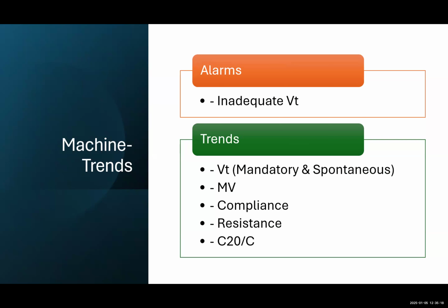Trend means I might come in the morning at 8 o'clock or 9 o'clock for my rounds, but how was the baby from the night, 12 o'clock to 8 o'clock? The machine gives me a record. In this, the alarms are very important. If the machine is alarming for inadequate tidal volume, that means either the lung is worsening or there is a leak, and you should identify and correct it.